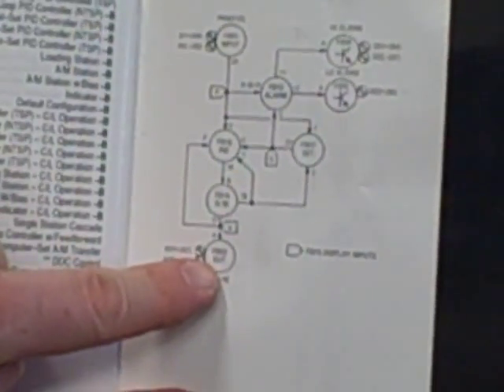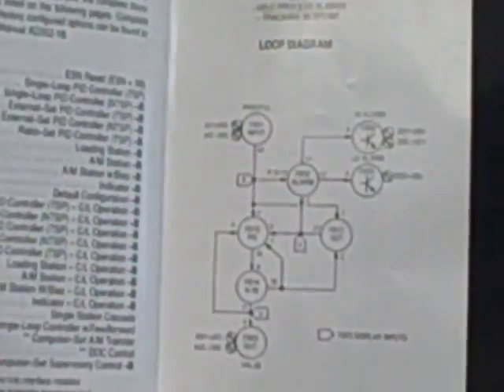Now in the Model 352 controller, each function block has a unique number. Function block one is always the analog in. Function block three is always the analog out. Function block 13 is always PID, etc.